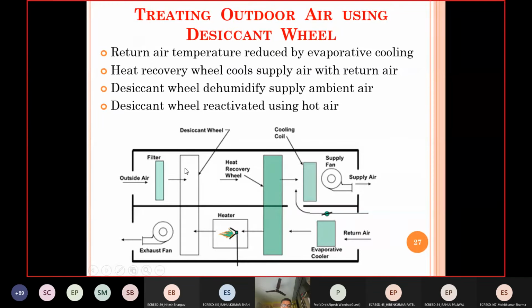When it absorbs moisture here, it will become saturated, and the moisture has to be removed in this portion when it is continuously rotating. So here you are heating this air, and you are removing that moisture from this wheel, and then the air is exhausted. Okay, so once this gets regenerated, as it is called, it goes into the other part, and it has capability to remove moisture from here.